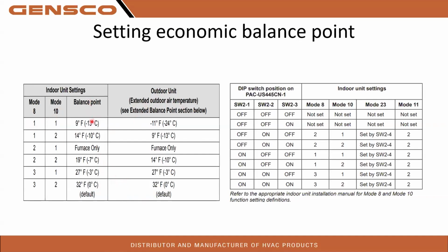So if you have a standard furnace, these are your options right here: 32 degrees, 27, 19, furnace only. So if you guys are using a PUY, cooling only outdoor unit, you're gonna wanna make sure to set this to furnace only. That way it doesn't try running the heat pump. 14 degrees and 9. And then for your extended balance points, this right here is if you have a hyperheat outdoor unit, your balance point changes. So you can go all the way down to -11 with that. So again, this would be set up through your MHK2, function code 8 and 10. And you'll find this in your install manual for the PAA coil.